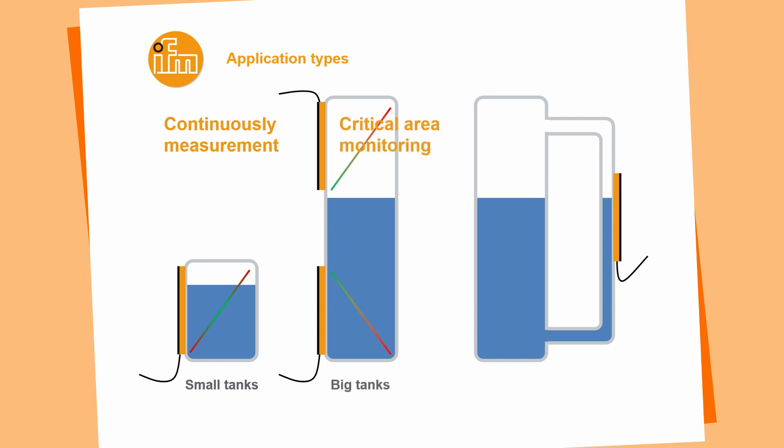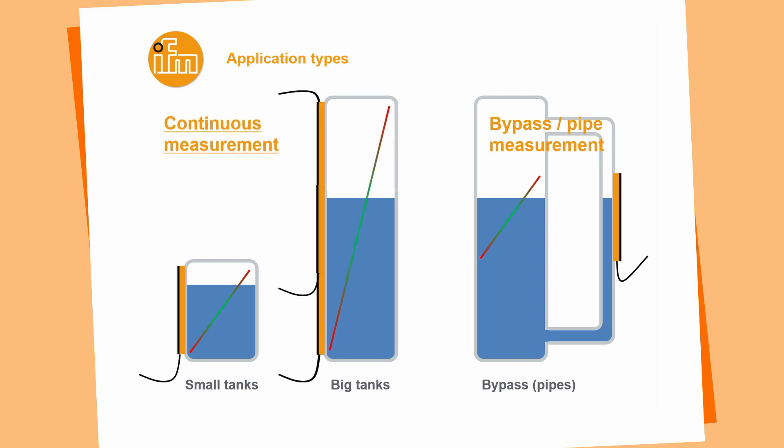We can use the sensor for critical area monitoring, that means for high and high high application or for low and low low application. We can use the process value of the sensor or we just use the switch points and save sensors, because we just need one for one critical area. Like I told you before, we are also able to measure a level inside of a pipe or a bypass. In a bypass the level is always similar to the level inside of the tank. If we have larger tanks, for example 800 millimeters, we are able to use more than one KQ10. We just take in this case three sensors, mount the three sensors on the tank and we are able to see the process value from zero at the ground of the sensor to 100% at the top of the sensor.